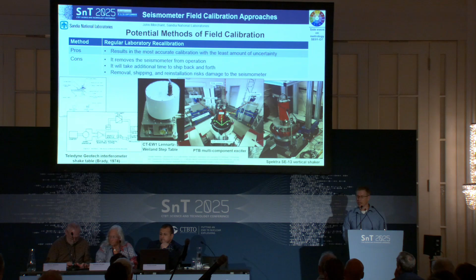There have been some presentations by Thomas and others on these methods of laboratory calibration, and some people propose just send the instrument back and be calibrated, and really that's not a good alternative. It requires the instrument to be removed from service. It requires it to be shipped. That's very detrimental to the hardware, and we don't want to be doing that. So despite the fact that we have these great capabilities in the labs, they're in the labs, and they're not in the field where we need them.